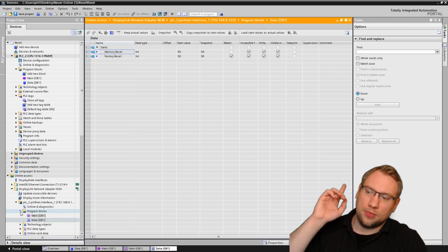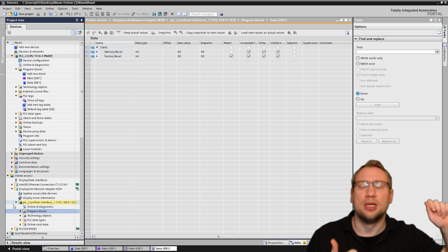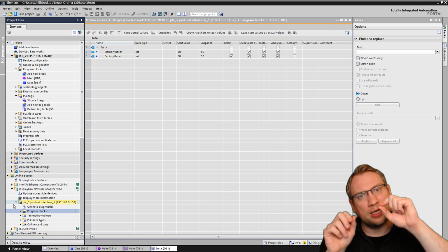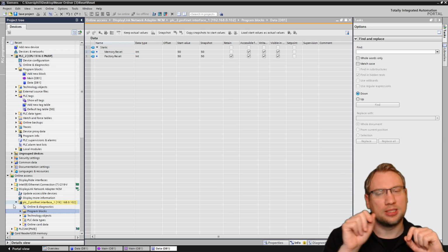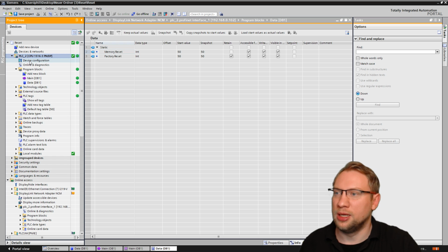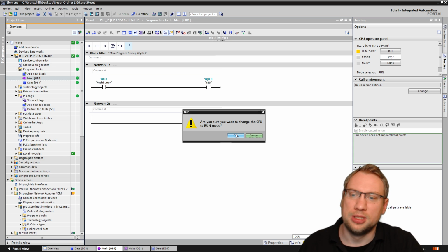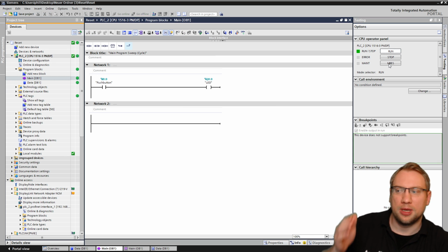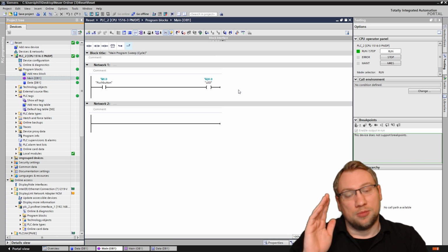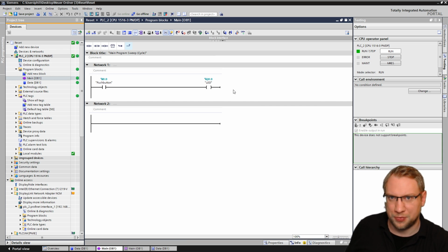So we had the reset from stop status to the start, right? When you reset the PLC, that's just a reset. Then we have a memory reset. When we do the switch down, blink twice, switch it to the center, switch down, blink fast, or in the software when we go online, we have to be on the PLC, and in testing, we go MRES, memory reset. Right, MRES, that's the same as with the switch. If we do it in the software or with the switch, no difference. Right, no difference at all. Memory reset. And we have a third reset that is stronger. Right, that is a little bit stronger.